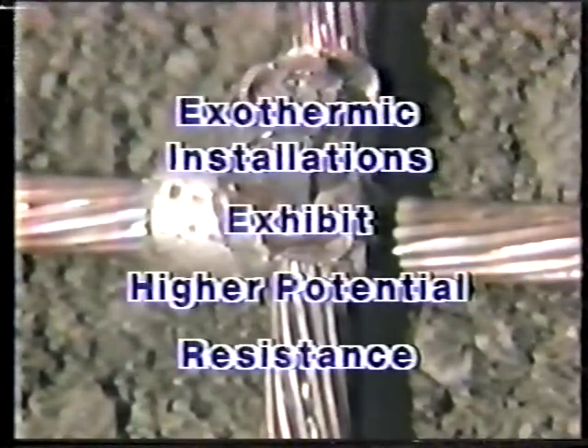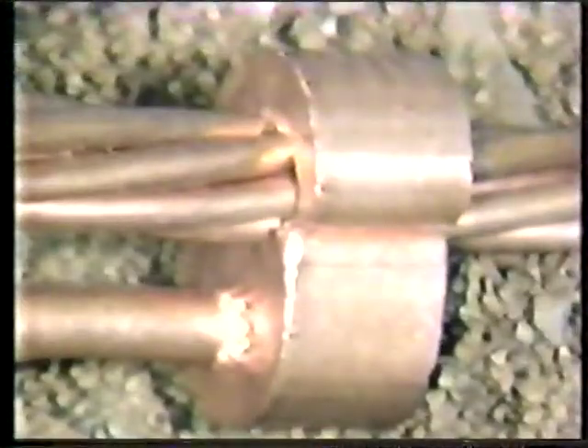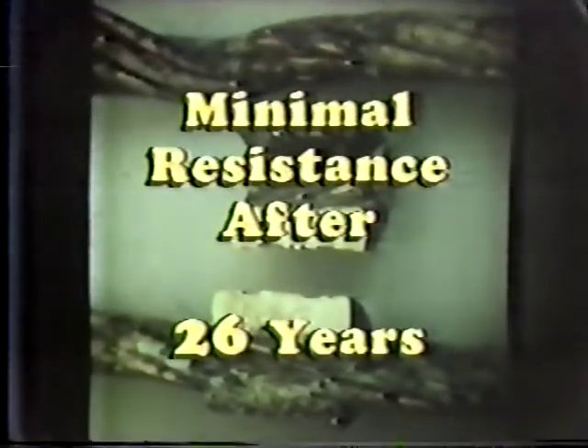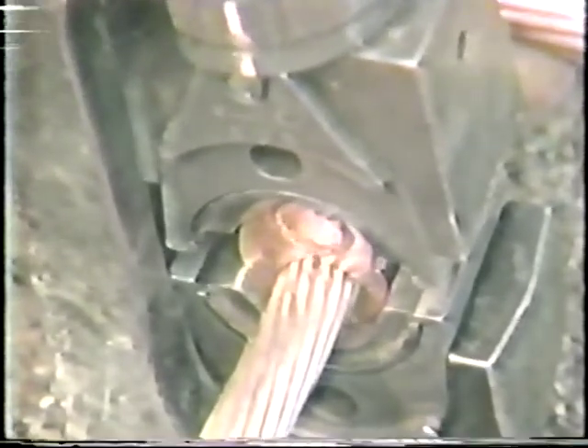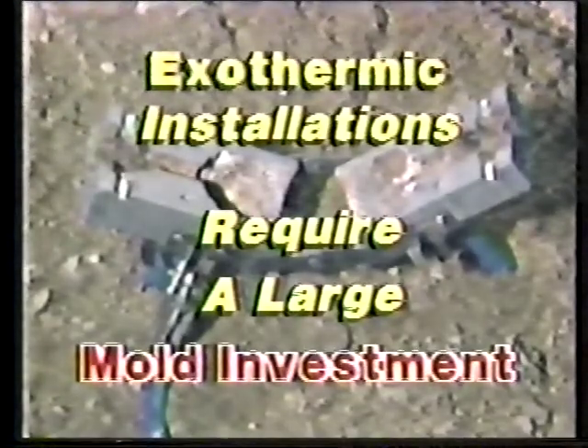Exothermic installations, on the other hand, require a different alloy material, creating the potential of higher resistance joints. When you consider the potential for improper exothermic installations, the repeatability of compression connections truly shines. In fact, some 26-year-old compression connections exhibit a resistance similar to the conductor itself. The Hyground system can be installed with either hand tools or high-volume power compression tools. To ensure consistency, these installation tools will automatically release, producing an audible blow-off when the installation is complete. A Burndy installation requires less than 5 minutes to complete, whereas the exothermic process will take approximately 15 to 20 minutes per installation, almost 3 times as long. Exothermic systems also require a large investment in special molds for each conductor size and connector type.